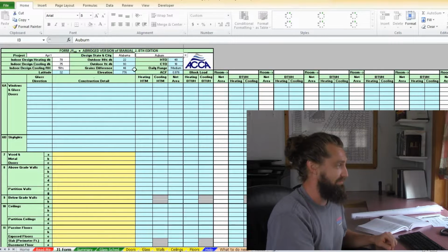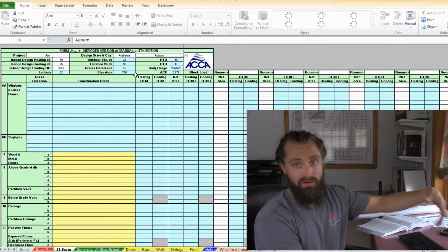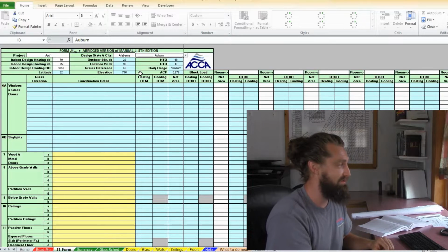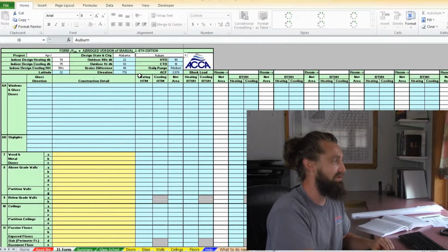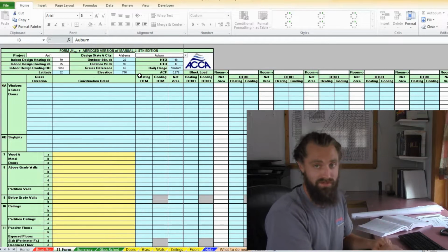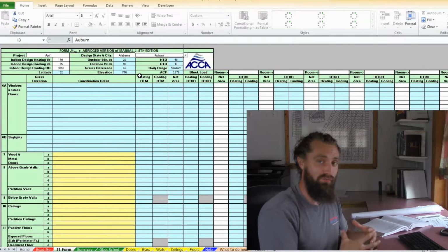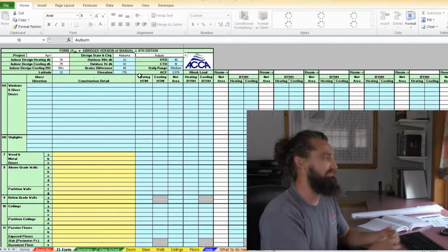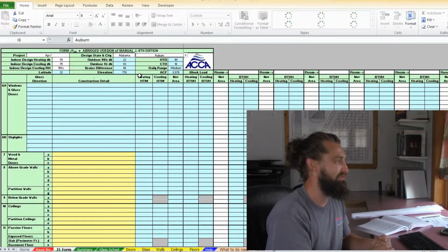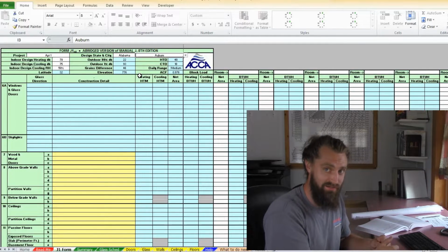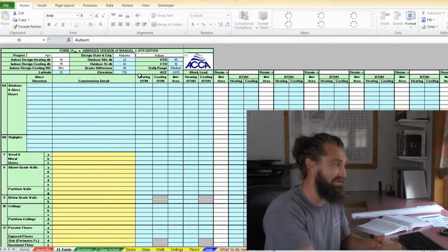Directly below Alabama, you can see our outdoor 99% dry bulb temperature, 22 degrees. That's what we're sizing our heating system on. Directly below that, we've got our outdoor 1% dry bulb, which is what we'll size our air conditioner on, 93 degrees.